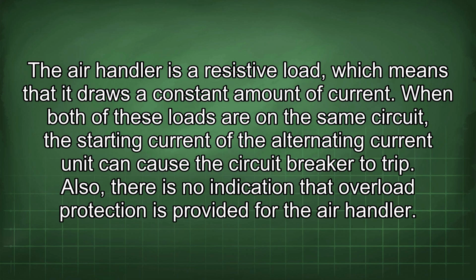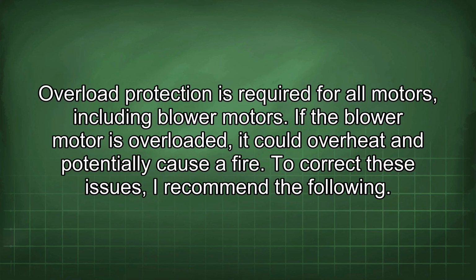Also, there is no indication that overload protection is provided for the air handler. Overload protection is required for all motors, including blower motors. If the blower motor is overloaded, it could overheat and potentially cause a fire. To correct these issues, I recommend the following.